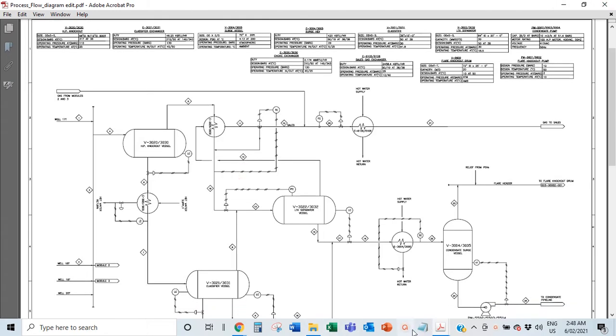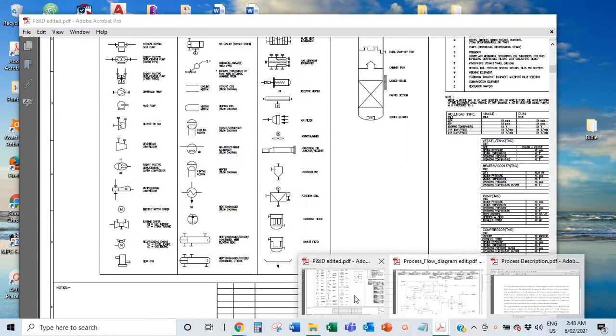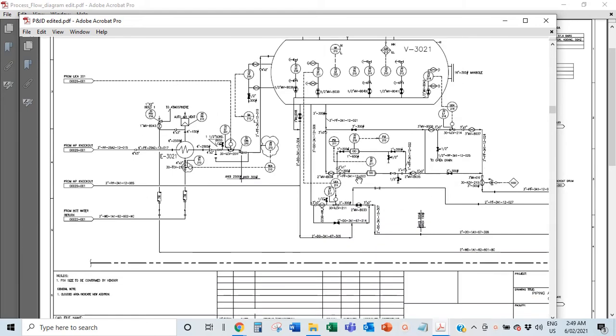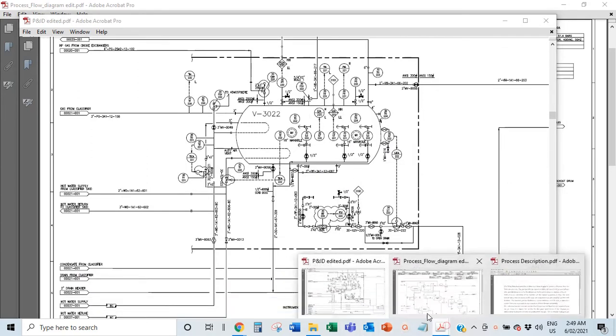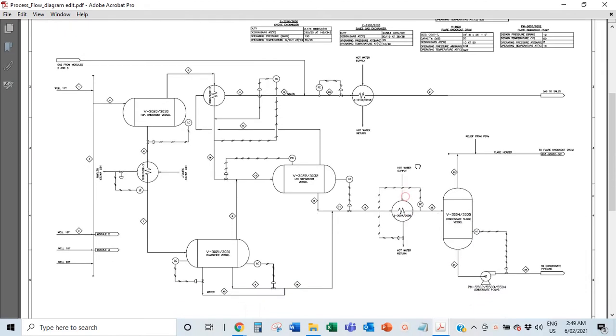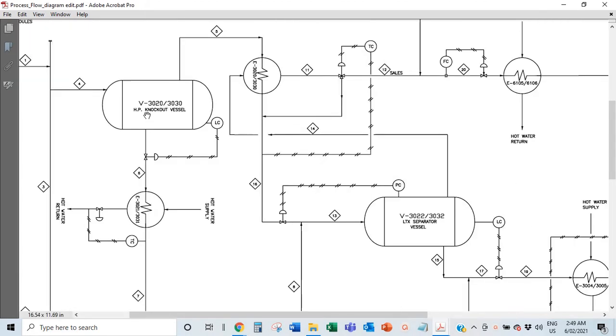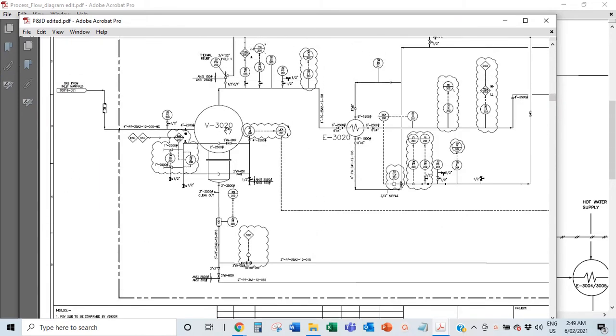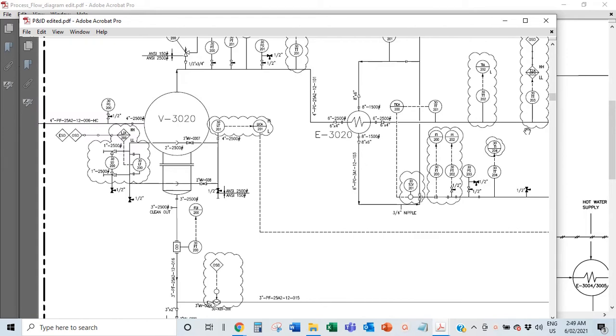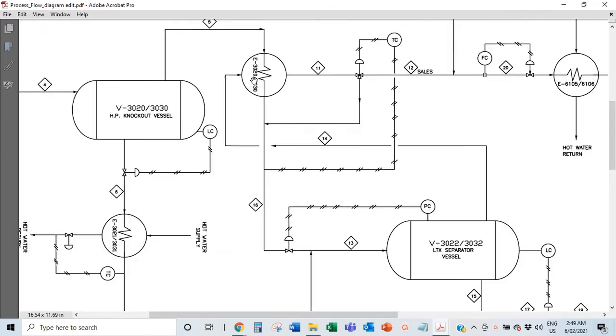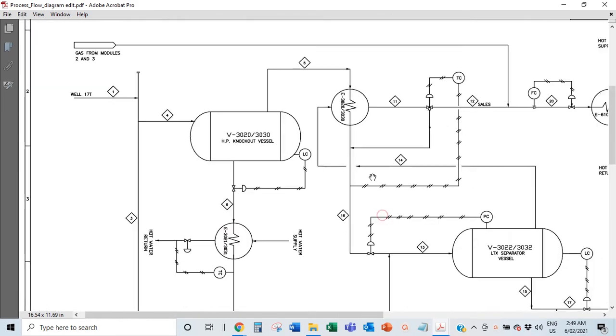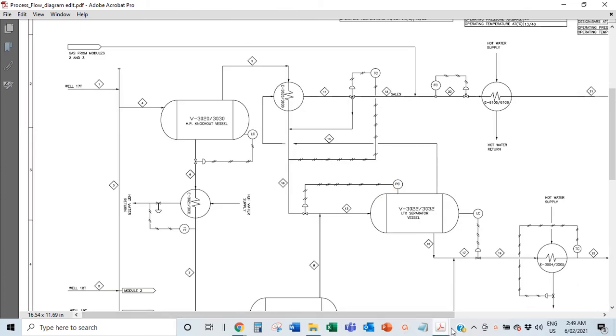A PFD is a process flow diagram — it's like a P&ID but with a lot less detail. Everything you see across all these pages of the P&ID shows up in the PFD. What you really have are the major equipment — like this vessel V3020 and heat exchanger E3020, which you can find on the P&IDs. All major equipment in your P&IDs should appear on your PFDs.